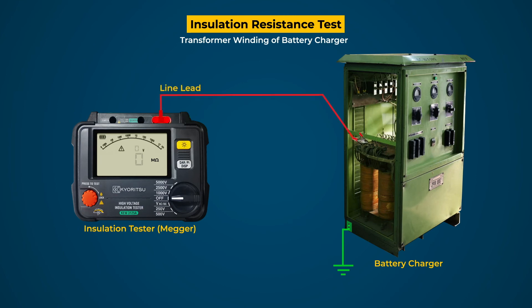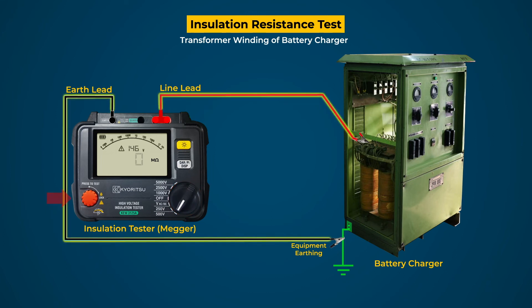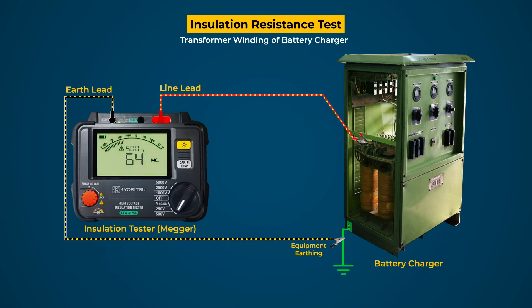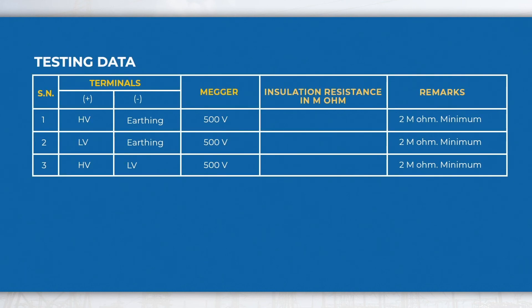Connect the line and earth terminal of the tester to the HV terminal and equipment earth through leads respectively. After that, check all the connections and select the test voltage level to 500V. On pressing the test button of the tester, 500V DC voltage is applied across HV and earthing. As a result, leakage current will flow in the circuit and the tester will measure this leakage current and calculate the insulation resistance by the ratio of applied voltage and measured leakage current. Do the test for these combinations and testing data may be recorded in this format for further investigation and future reference.